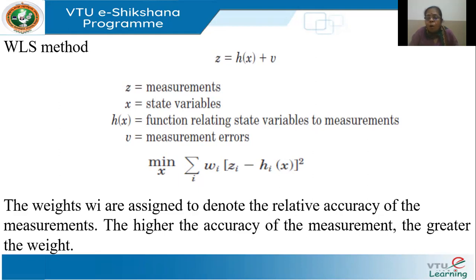Clear? Now, all my measurements may not be accurate. There are some instruments which, if you want them to be very accurate, are very expensive. So in installing the measurement devices, we make a trade-off between cost and accuracy. If I know that the instrument is of higher accuracy, then I give it a higher weight. Instruments of lower accuracy we give a lesser weight. So this minimization is the objective function. And there are different optimization algorithms to minimize the objective function. So this is the problem of weighted least squares.